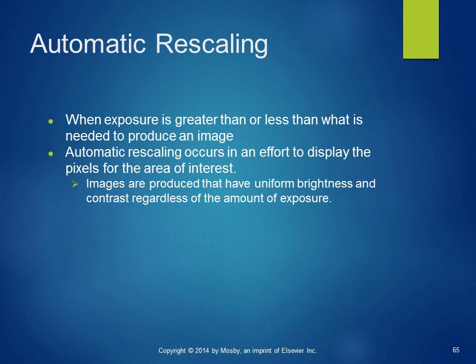Automatic rescaling. When exposure is greater than or less than what is needed to produce an image, automatic rescaling occurs in an effort to display the pixels for the area of interest. Images are produced that have uniform brightness and contrast regardless of the amount of exposure.